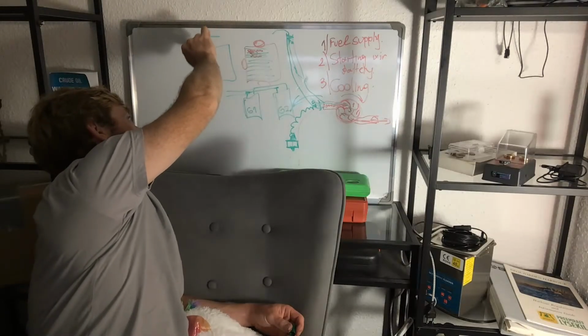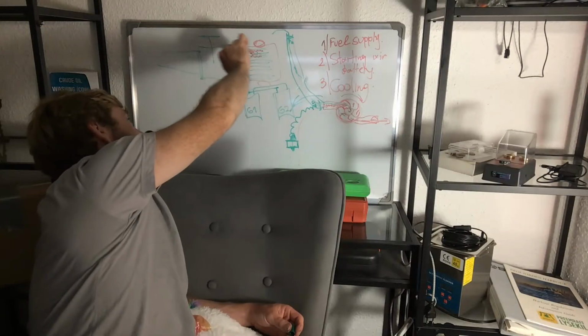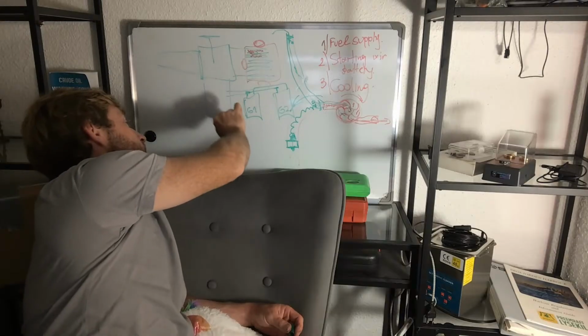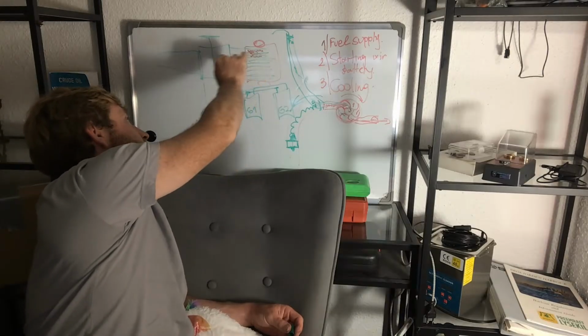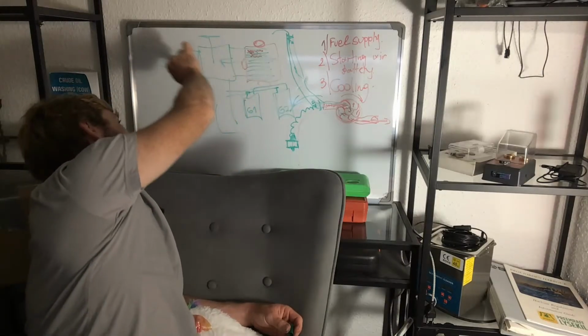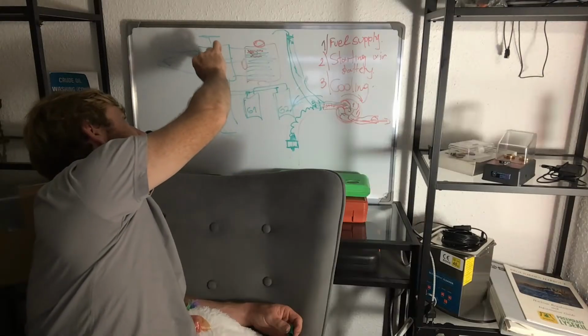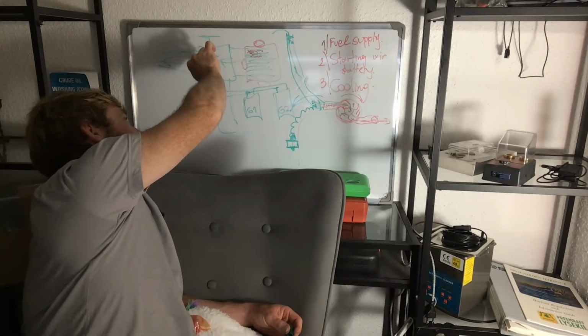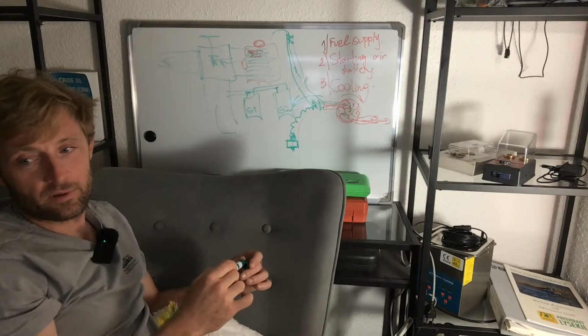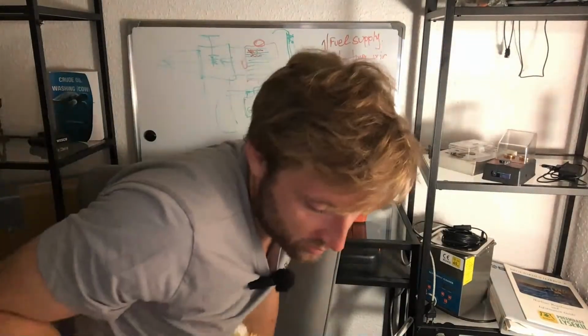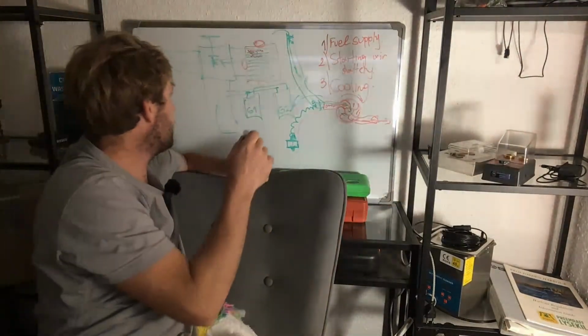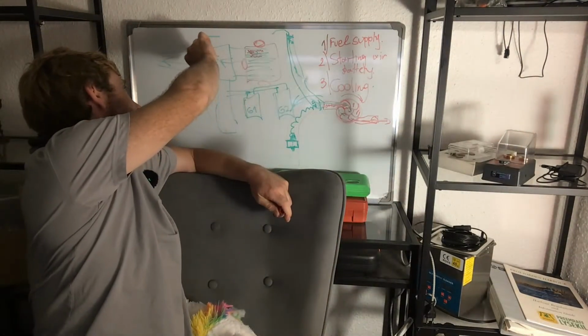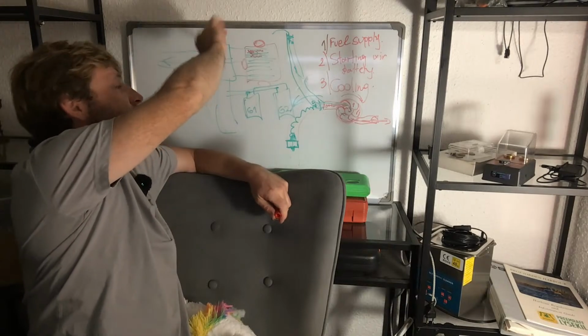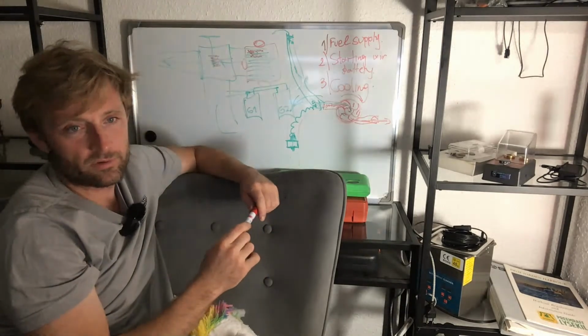Because this is the valve here, this is the three-way valve. This is going to the engine, probably, so recirculating inlet, outlet, and recirculating. So you have to check the indicator here, if it's moving or not, if it's giving the proper signal to the valve and activating it. So all these things, yes, you have to check.